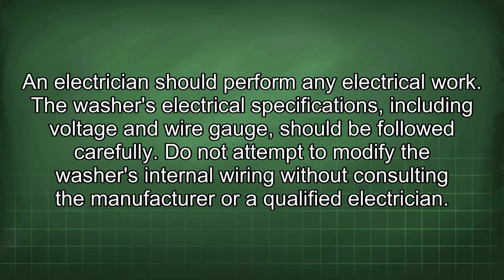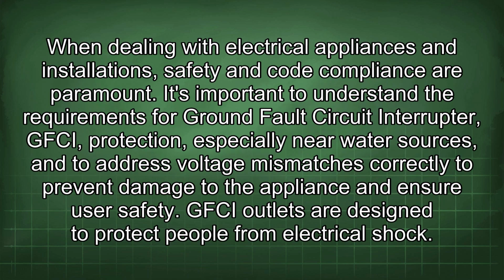An electrician should perform any electrical work. The washer's electrical specifications, including voltage and wire gauge, should be followed carefully. Do not attempt to modify the washer's internal wiring without consulting the manufacturer or a qualified electrician. When dealing with electrical appliances and installations, safety and code compliance are paramount. It's important to understand the requirements for ground fault circuit interrupter (GFCI) protection, especially near water sources, and to address voltage mismatches correctly to prevent damage to the appliance and ensure user safety.